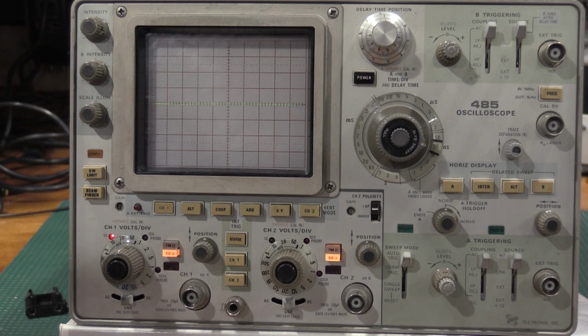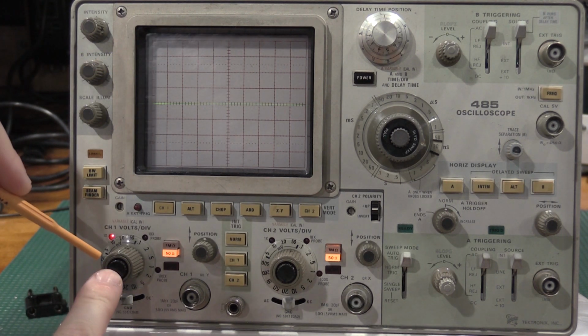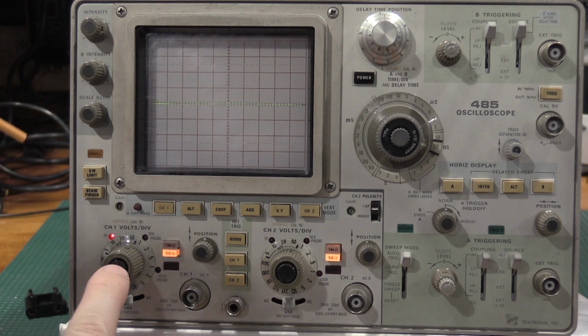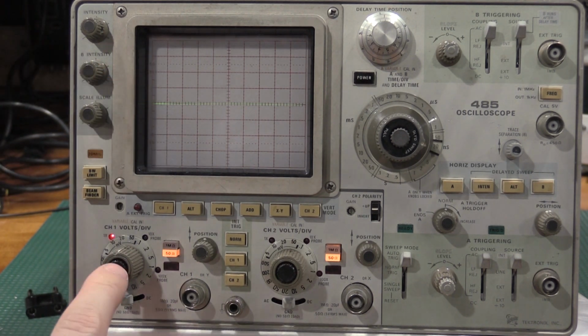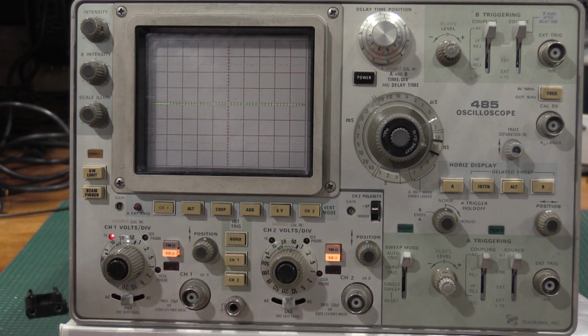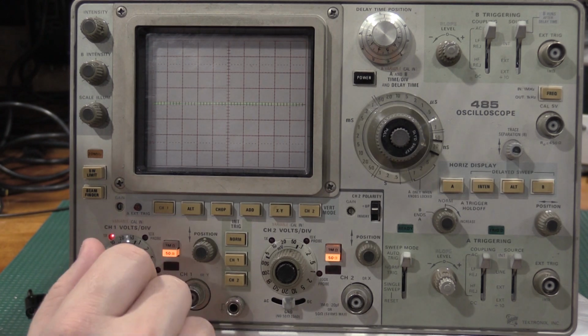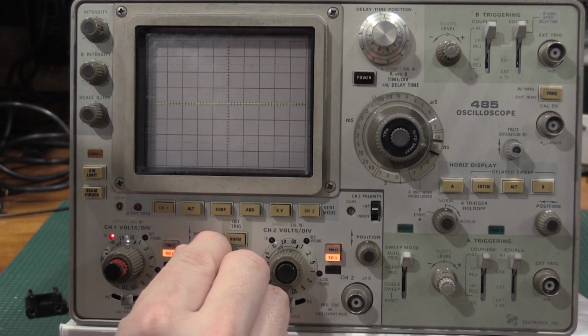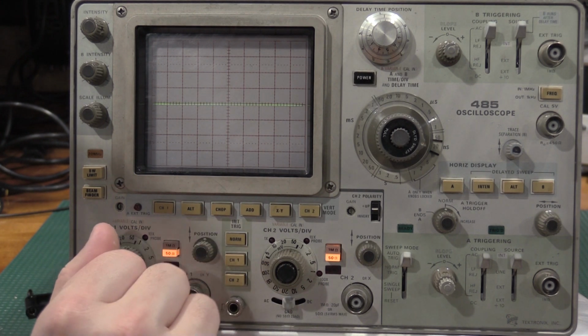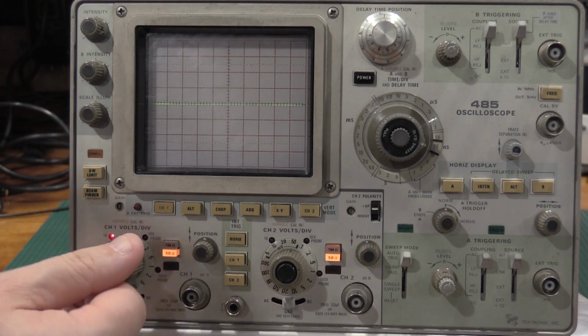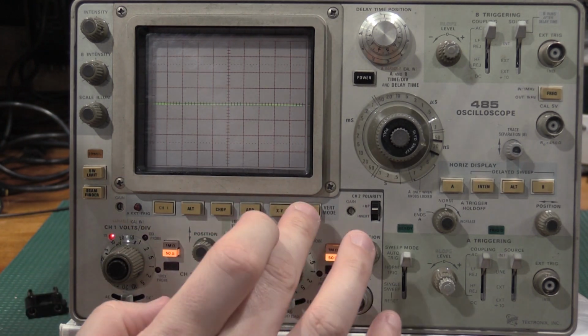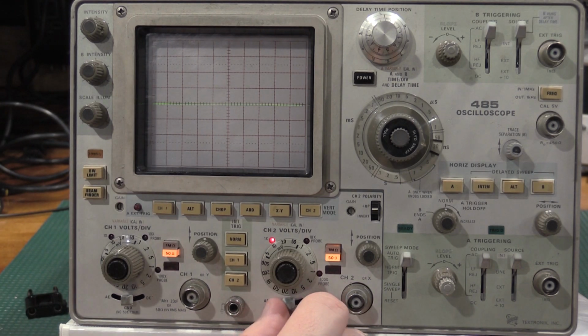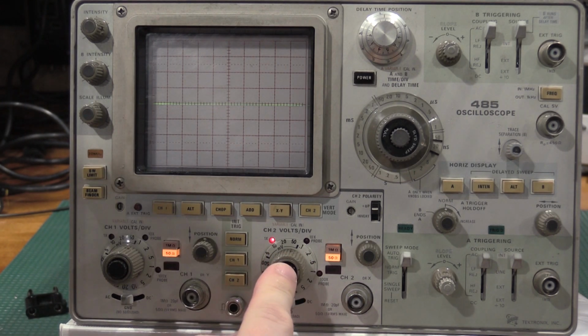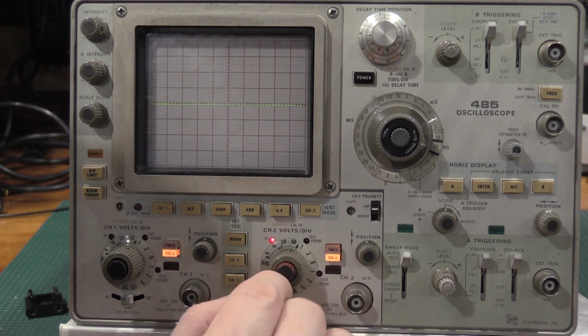And for the variable balance, when you're shifting from cal to uncal, this is uncal, this is cal, you want less than a 0.1 division shift. We have that, so we're good. And then if I rotate this, so if I bring this down to the center line, if I go 100% through the range, it shouldn't move more than 0.2 divisions. It doesn't, so there we go. Check the same for channel 2. Doesn't move.